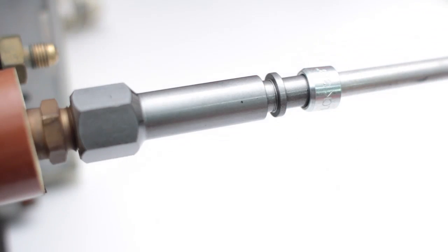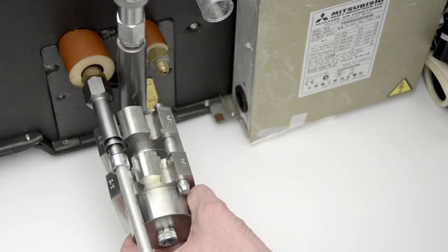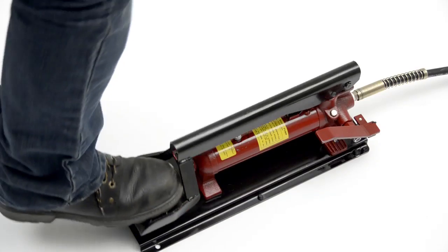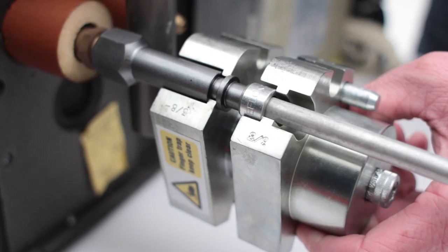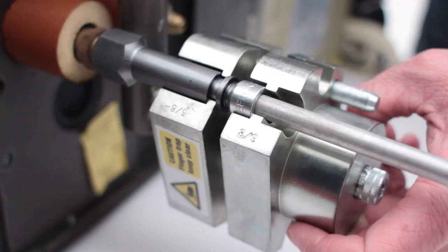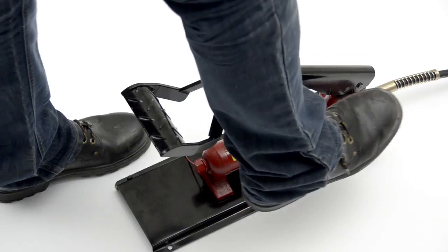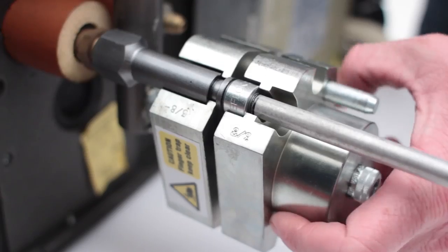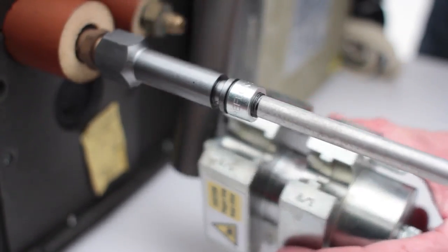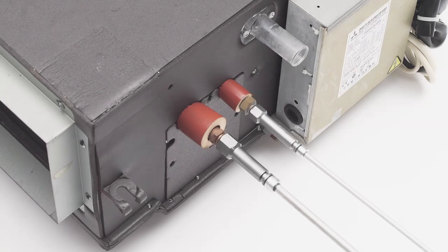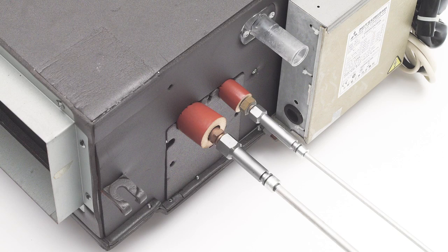Offer up the nut to the body of the joint. Locate the body of the joint and the nut in the jaws of the tool. Begin pumping the foot pump and keep pumping until the nut is fully home and the joint is made. Release the pressure at the foot pump and remove the tool from the completed pipe joint.